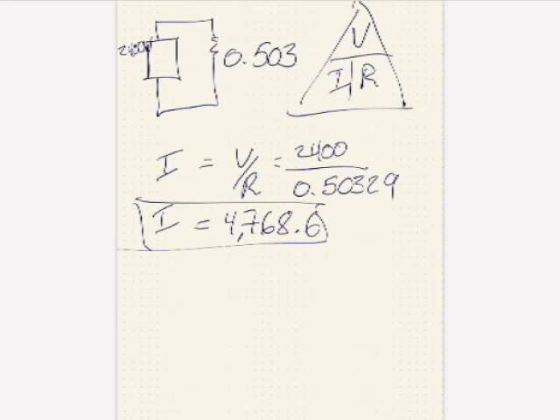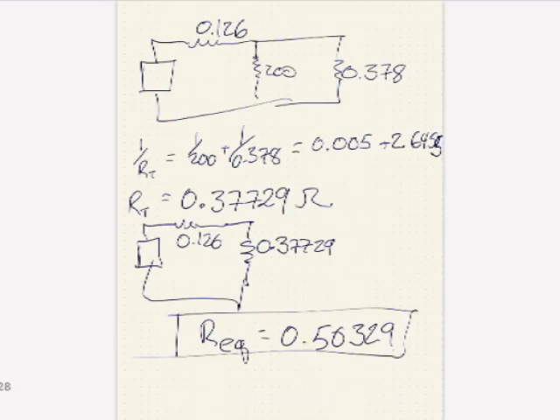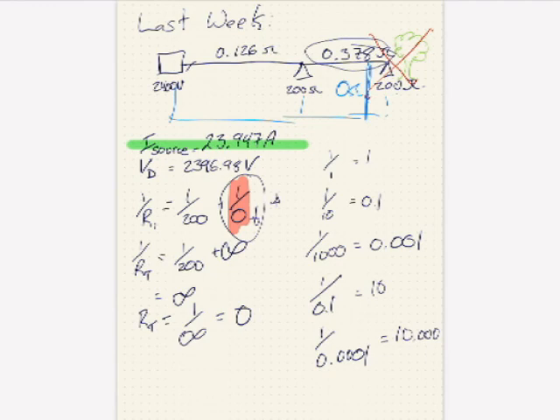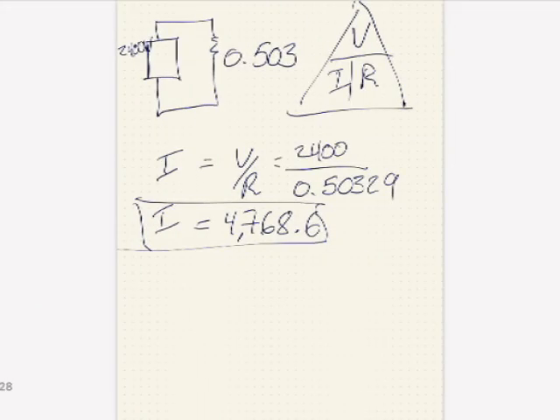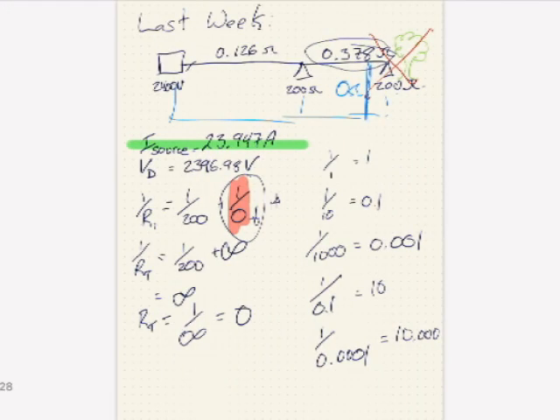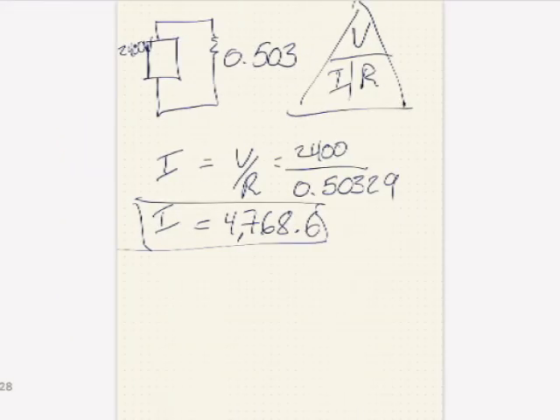We also see that in practice, our two load transformers don't really contribute at all. The only contributing factor is the resistance of the line itself. Had this fault occurred closer in, you can imagine had the fault occurred at the first transformer instead of the second, we wouldn't have this 0.37 here. We'd see almost 4 times the amount of current flowing.